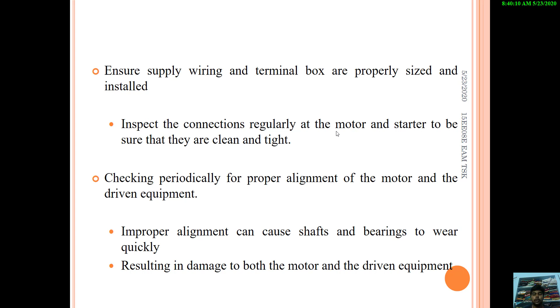Inspect the connections between the motor and the starter regularly to be sure that they are clean and tight. Also check alignment, because improper alignment can cause shafts and bearings to wear quickly, resulting in damage to both the motor and the driven equipment.